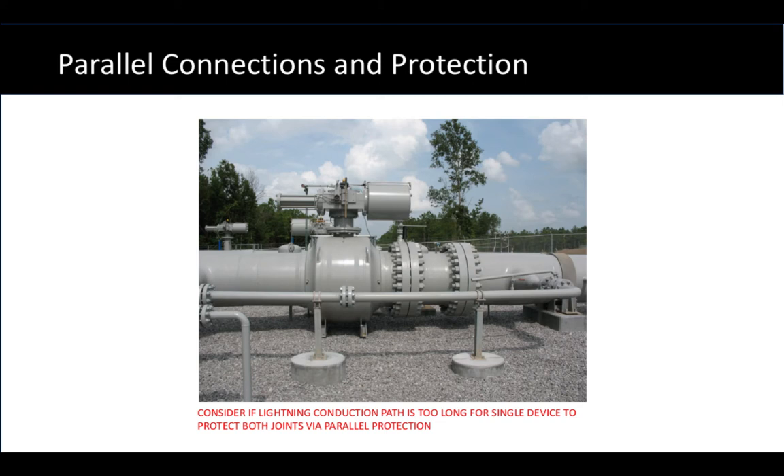The example of where you'd have such a situation is where the main pipeline with an insulated joint has in parallel with it a bypass or a run with another insulator. One would have to consider the incidence of lightning for your proposed installation and whether the inductance of this other bypass path is excessive and therefore might need its own decoupler across that insulated joint.